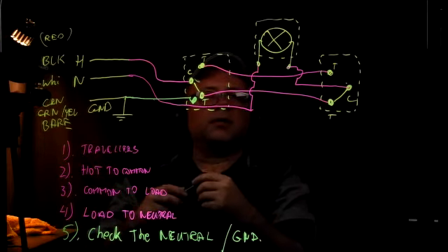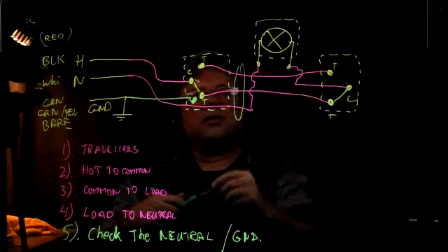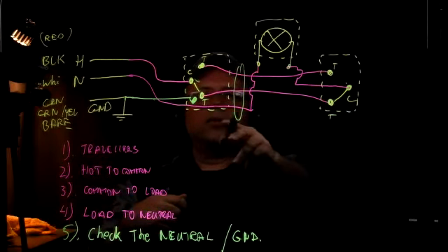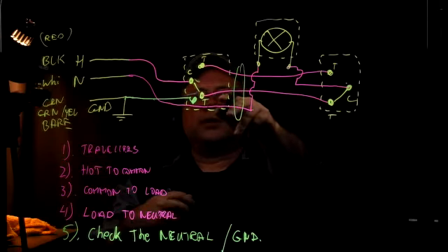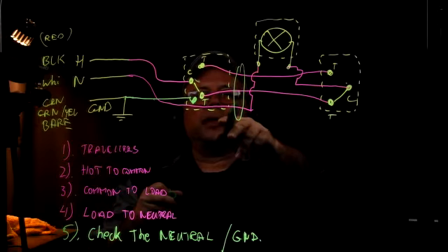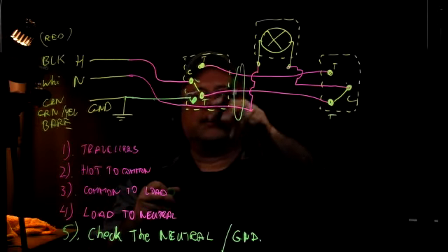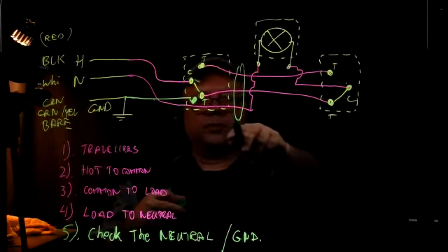So what do we have? How many wires do we have here? We just have 3 wires going there, white, and two hot ones. So it could be 14-3, right? Because of white, black, and red. Plus neutral, plus the ground.